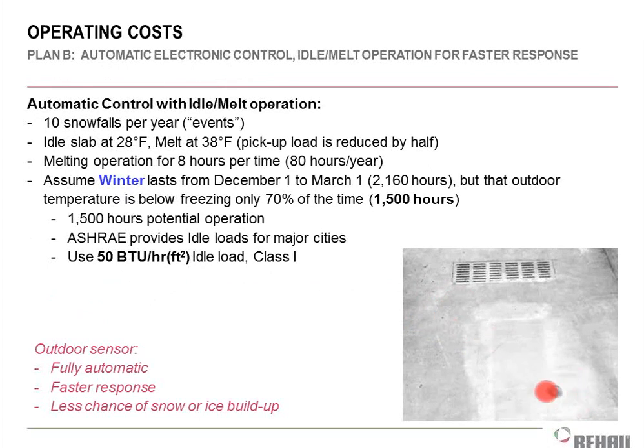There's a picture of that hockey puck sensor I was talking about. Typically you bury that in the concrete, right? We use the other kind when you forget to bury this one in the concrete. But it works in a similar fashion. I'm detecting that slab temperature and deciding if I'm going to have a snow melt event or not.